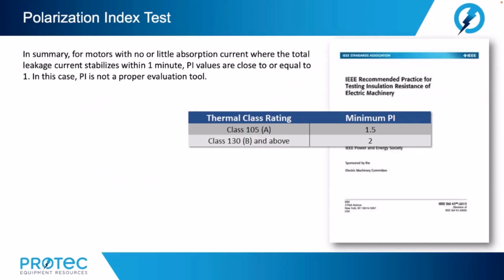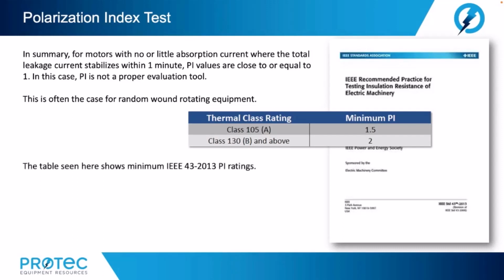In summary, for motors with no or little absorption current, where the total leakage current stabilizes within 1 minute, polarization index values are close to or equal to 1. In this case, PI is not a proper evaluation tool. This is often the case for random wound rotating equipment. The table seen here shows minimum IEEE 43-2013 PI ratings.